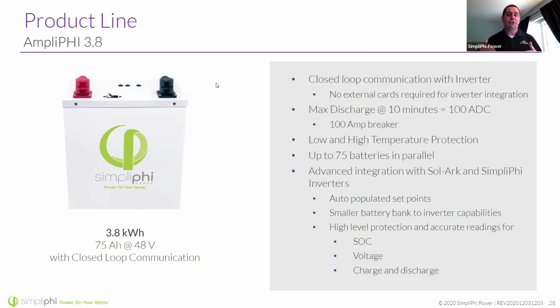It also has temperature protection. It can tell the inverter, based on its internal temperature, to throttle back charging at low temperatures. So there could be an exception where, due to a very slow charge rate, you might be able to continue charging below freezing because the BMS is communicating to your inverter. Likewise, it could tell the inverter it's getting too hot and it needs to stop discharging as much.